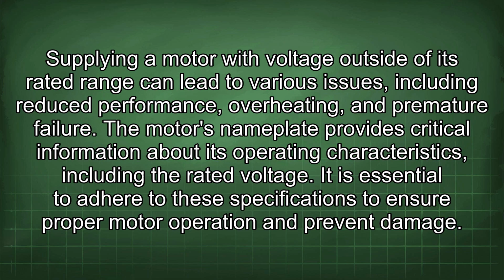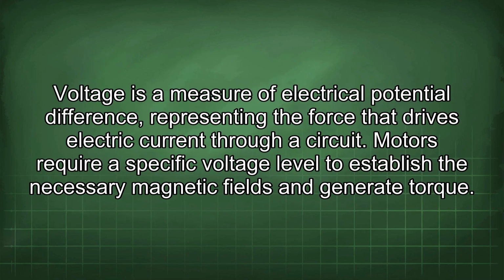Supplying a motor with voltage outside of its rated range can lead to various issues, including reduced performance, overheating, and premature failure. The motor's nameplate provides critical information about its operating characteristics, including the rated voltage. It is essential to adhere to these specifications to ensure proper motor operation and prevent damage. Voltage is a measure of electrical potential difference representing the force that drives electric current through a circuit. Motors require a specific voltage level to establish the necessary magnetic fields and generate torque.